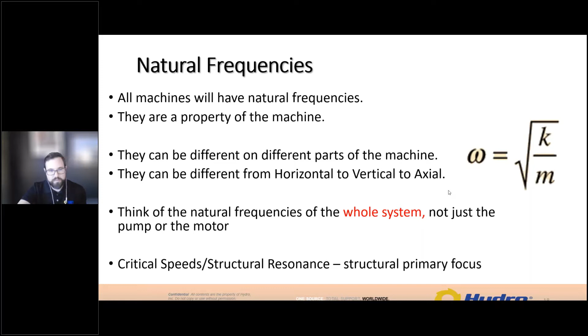In order to have a resonance, there also has to be a forcing frequency. Forcing frequencies are the vibrations or frequencies that come up as a result of operating the machine. If you have a little imbalance, that shows up as a particular frequency. If you have some misalignment, there's another frequency. Vane pass in a pump, for example, gives you a frequency too. So these arise due to the way the machine is run. You're driving the machine, forcing it to do work, and the resulting vibrations are the machine's forcing frequencies.